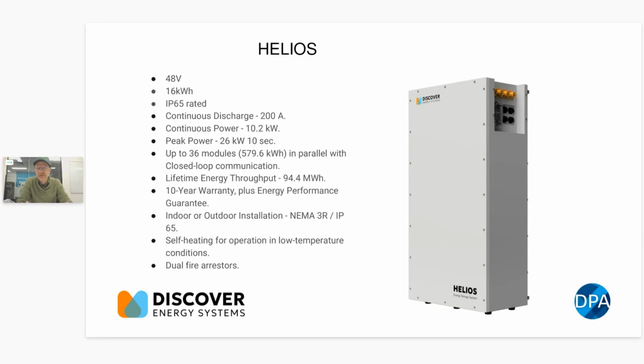The peak current is 300 amps for 15 seconds, and you don't really want to be going above that, and that would pair it pretty well with like an 8 kilowatt inverter. You could use a 10, but it would be the surge. If it was a 10 Noark, it doesn't have much of a surge on it, that would be okay. But if you're looking at like a Victron 10 kilowatt, the surge might be getting a bit high for it. It would work some of the time, but in terms of your design, I probably wouldn't be designing it to be right on the edge like that.